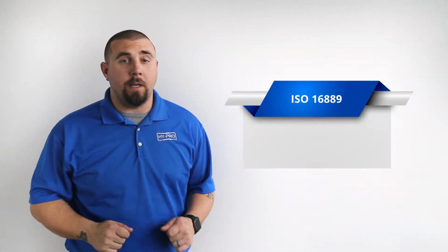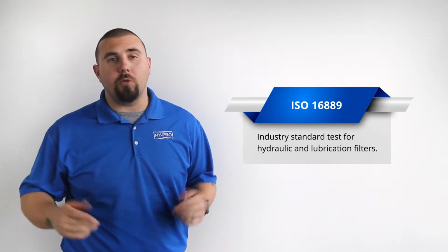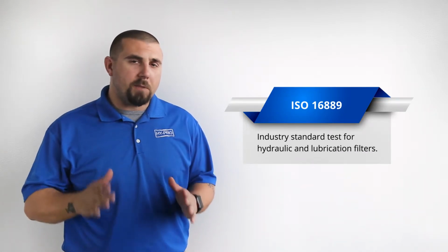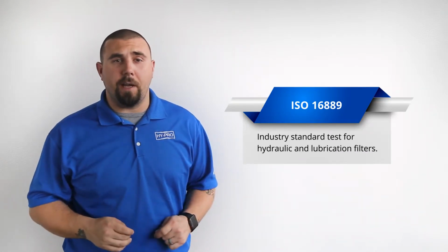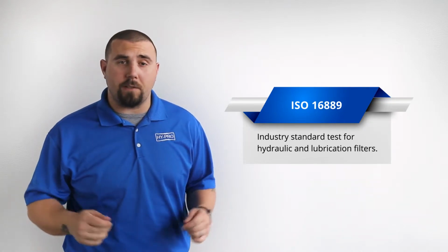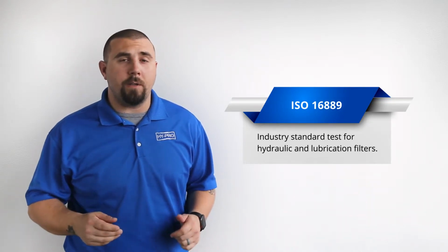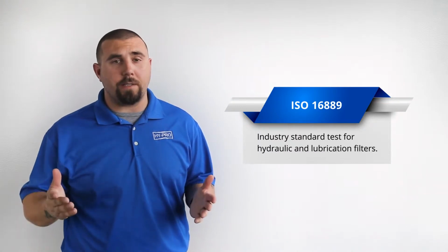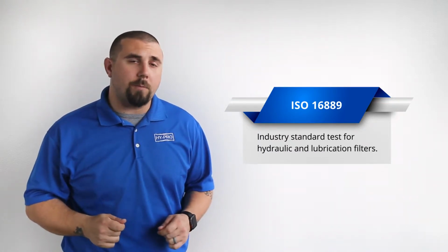ISO 16889 is the industry standard test for hydraulic and lubrication filters. Its main purpose is to detail the necessary aspects of design and construction of test stands, their application of contaminants, as well as the procedures used during testing. Here are some highlights of those aspects.